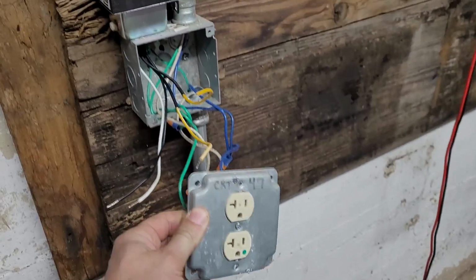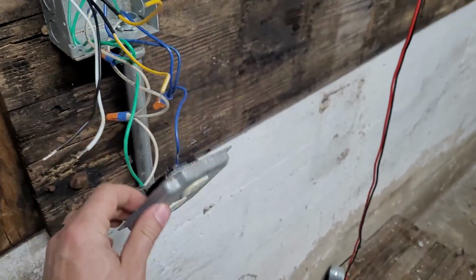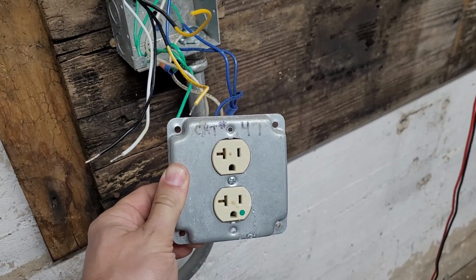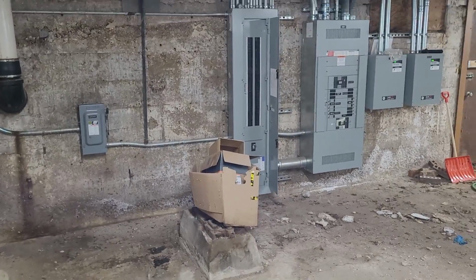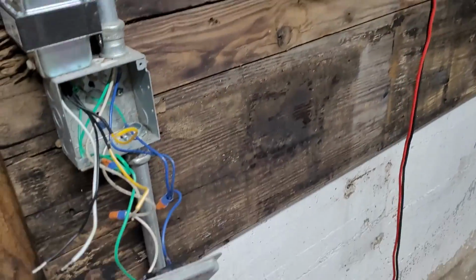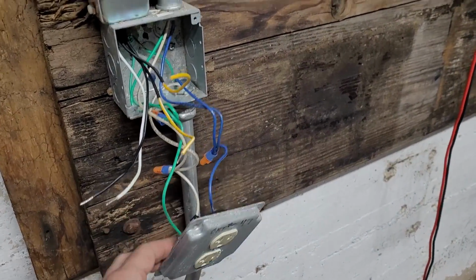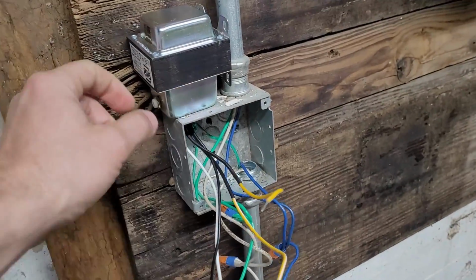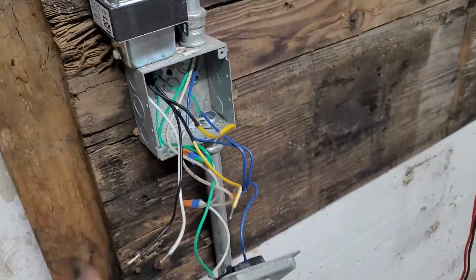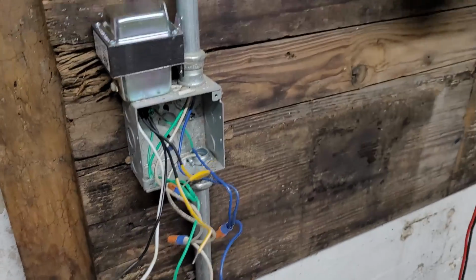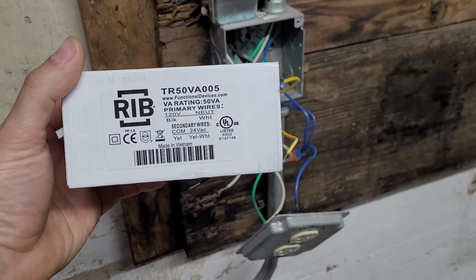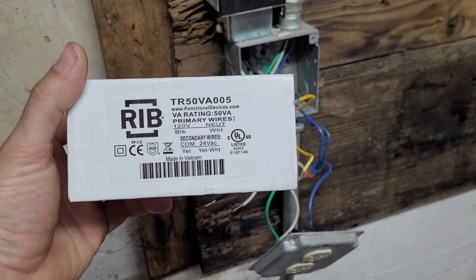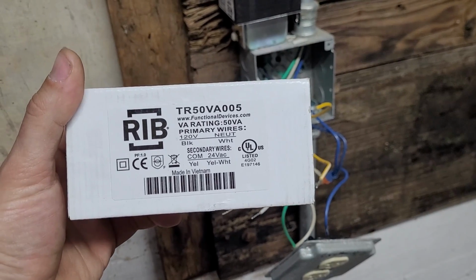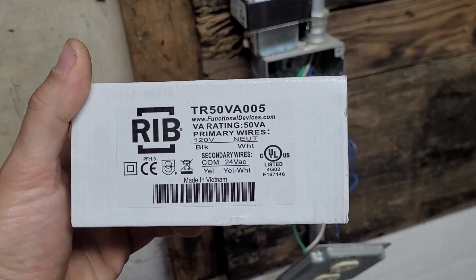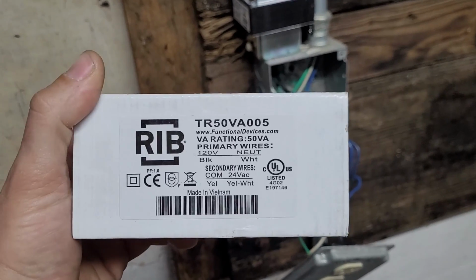So they made this really easy for me because they have a deep box, and they also mark circuit number 47, which is in the breaker panel over there, number 47. So I used my meter to verify that it was dead and pulled it out, knocked out one of these knockouts, and now I know it's 120 because all receptacles are 120 volt. So when I selected my transformer, I'm not going to use one of my more expensive multi-taps. I'm just going to select a transformer for the one that I need. I'm not going to waste a 277 480 transformer. I'm just going to select the one that I know I need and put it in.